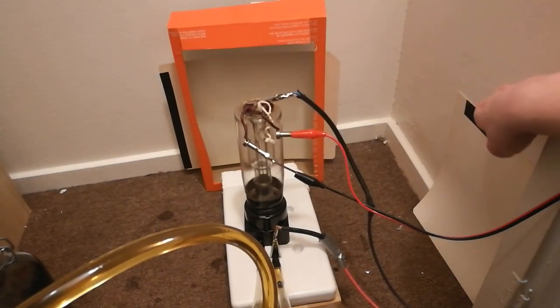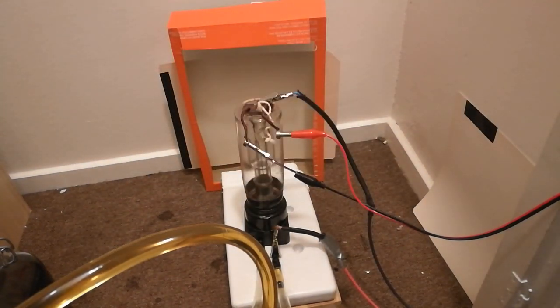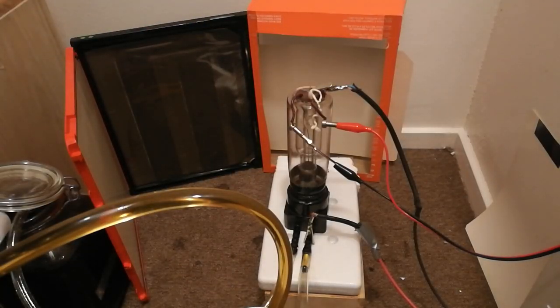I've got a bunch of screens set up — a blue intensifying screen right here, a green one over there, and I can set up another green screen which is in this extra cassette, just like so. Now you can see each of the beams in the form of visible light, which is pretty cool. I'll run it and you all should see some pretty decent glow, though this camera is very bad at capturing light in a dark environment.